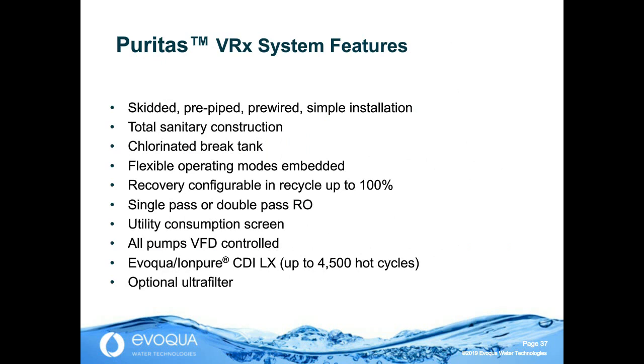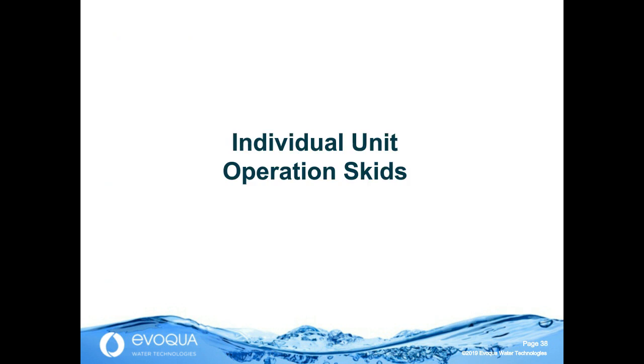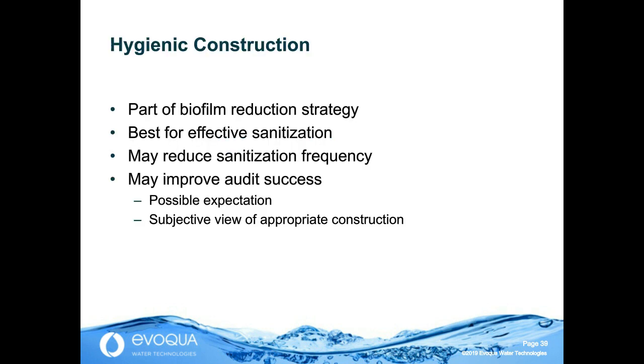If we move ahead to higher flow systems where an entire system on one skid isn't as practical, let's look at those skids a little and talk about construction. Hygienic construction may not be an explicit regulatory requirement, but it's a good part of biofilm control. It can make for more effective sanitizations. It frequently reduces sanitization frequency. And in an audit, you can't know what every auditor is going to expect. But look, stills are made in sanitary construction. So for alternative skids, it's logical to me to also do that.